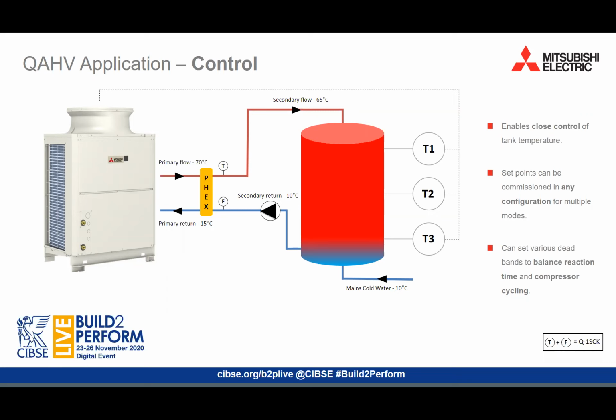The user may choose to turn the QAHV off when sensor T2 reaches 65 degrees or more, and then turn the unit back on when T2 reads 60 degrees or less. Equally, the target could be set to turn off at T3 at 65 degrees or more, and back on at T2 when that reads 60 degrees or less. The system can in fact be commissioned to operate in 3 different control modes, each with different on-off conditions. For example, the user may wish to have different control points at different periods of the day or night.